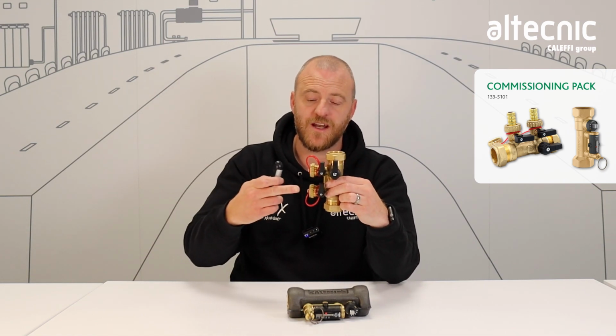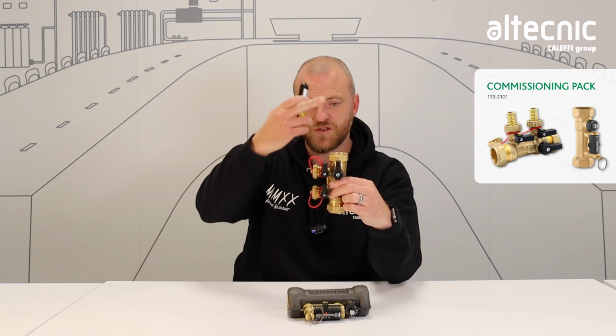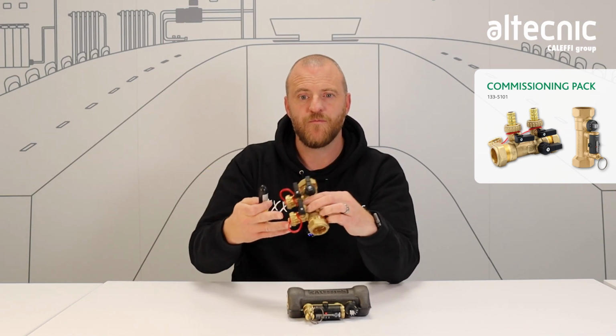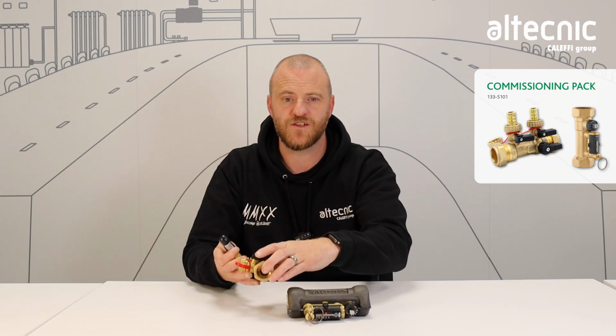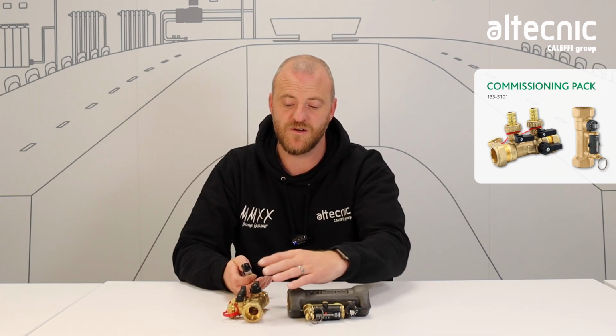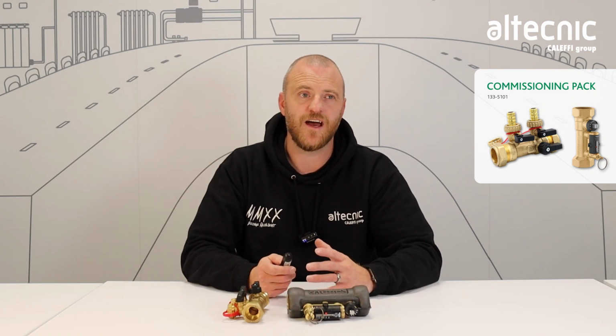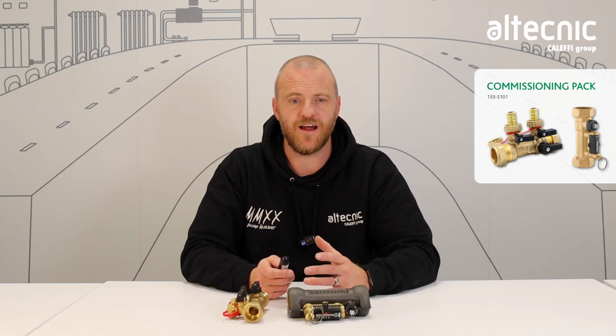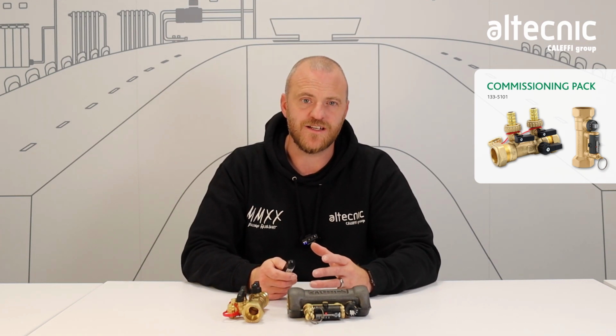So if you imagine this is installed on a system, you'll be able to connect onto one port, flush through and drain out of the other. By incorporating both isolation valves and diverting functions, the system is allowed to save a bit of space, save joints, and makes carrying out routine maintenance a lot easier.